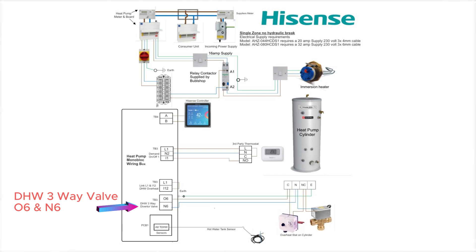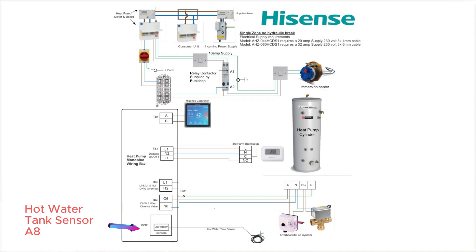This is our connection for the DHW motorised valve. Output O6 gives a 230 volt feed to the valve — it should be a spring return valve. And finally, your hot water tank sensor will connect into A8 on the sensor pockets.